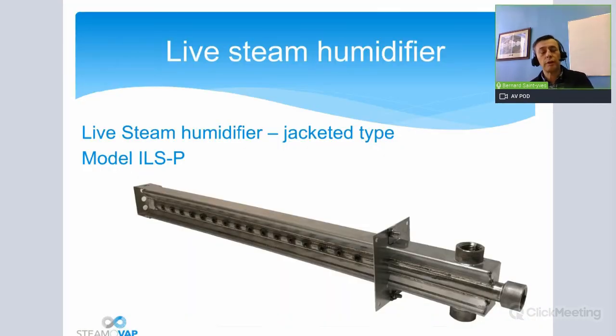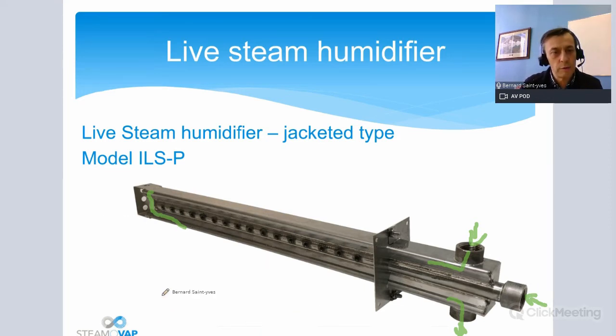So let's look at the product now. So this is a steam manifold with jacket from SteamOVAP. So you have one inlet here for the steam, and you have one outlet here. This is for the steam jacket. So what it is, a chamber heating the tube, heating the steam manifold, going around, okay, like this, here, and going back there, and then to the next, or to the steam trap. And then here, from the steam separator, we will come with the steam that will be injected or distributed into the airflow. The airflow would be this way, always against the holes.